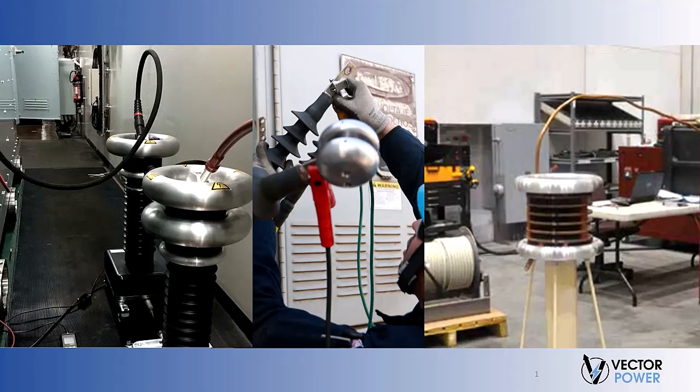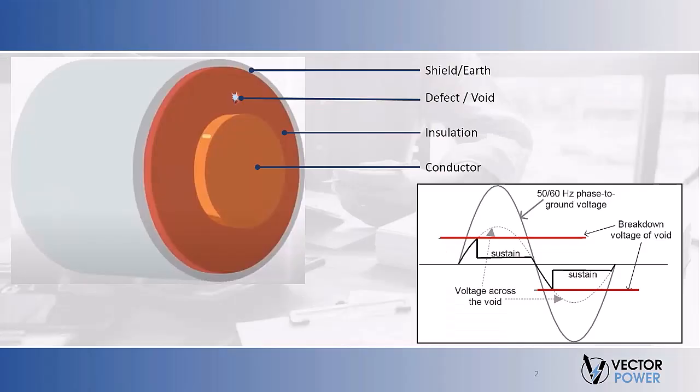Factory tests are conducted on unaged cables or accessories, while field tests are carried out on entire cable systems consisting of cables and accessories all installed together. Field tests involve systems with new and aged components, making them more challenging.